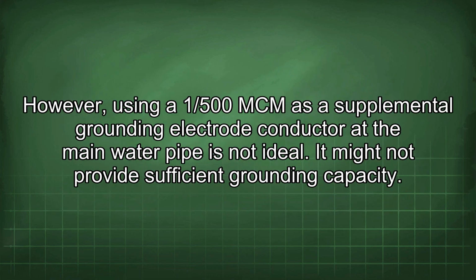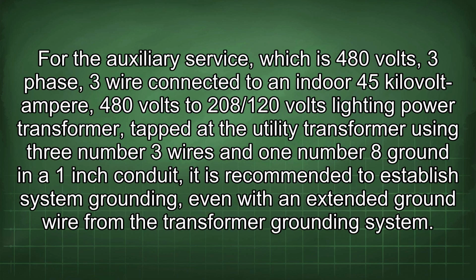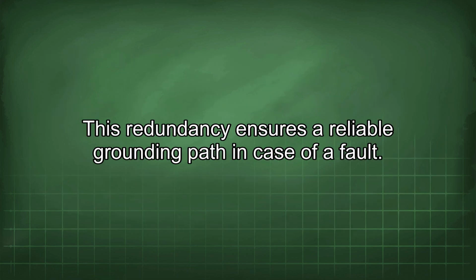However, using a 1/500 mcm as a supplemental grounding electrode conductor at the main water pipe is not ideal. It might not provide sufficient grounding capacity. For the auxiliary service, which is 480 volts, 3-phase, 3-wire connected to an indoor 45 kVA, 480 volts to 208/120 volts lighting power transformer, tapped at the utility transformer using 3 number 3 wires and 1 number 8 ground in a 1-inch conduit, it is recommended to establish system grounding, even with an extended ground wire from the transformer grounding system. This redundancy ensures a reliable grounding path in case of a fault.